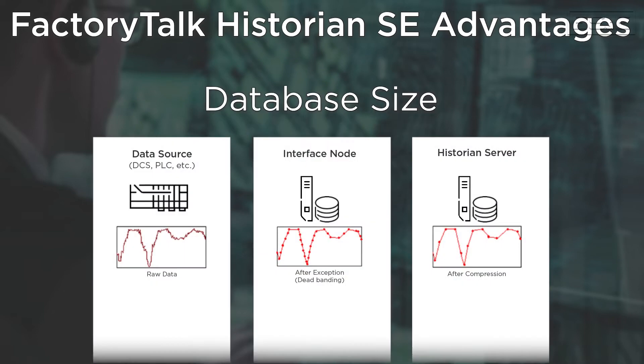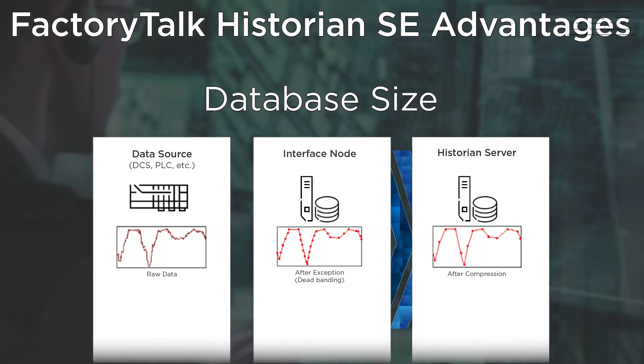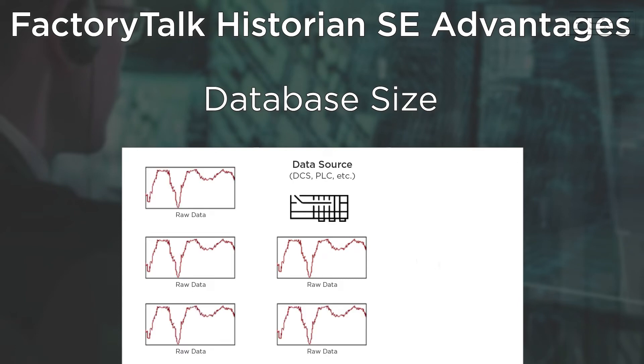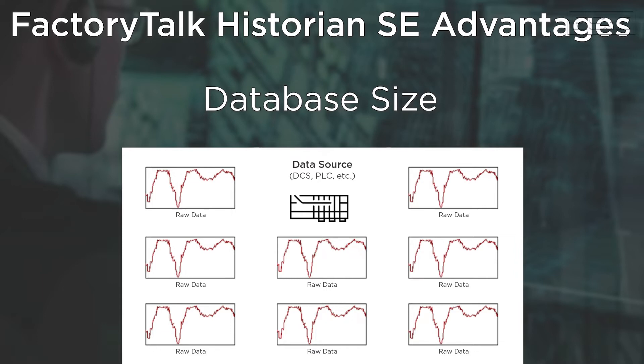Database size. One of the biggest advantages of the Historian SE is the way in which it compresses the data. It brings the data in from the controller, looks at those data values, and determines whether to actually store that value or not. After all, why would you store a data point that is not changing? Relational databases do not make that distinction — they store the data whether it's changing or not. The problem with that is you're collecting and storing data, consuming resources that aren't necessarily going to make a difference when you bring back that information to do analytics against it.